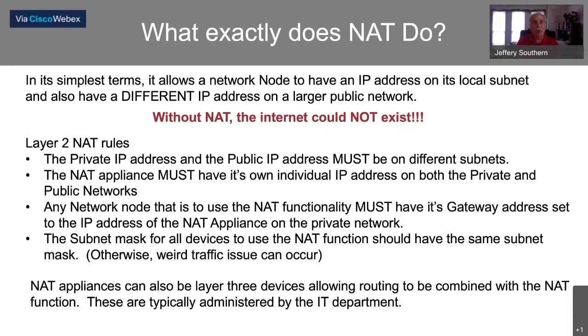I've seen this happen dozens of times, and it takes hours to figure out because you're looking at Wireshark and saying, well, I see where SCADA sent the packet requesting data from the processor, and I see where the processor responded, but it never went anywhere. It's because the subnet mask was set wrong, because somebody did it at some point and didn't understand, or didn't care at the time, why that might cause a problem in the future.